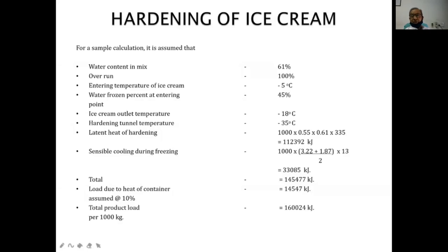The entering temperature of the ice cream is minus 5 degrees centigrade. We assume that at minus 5 degrees centigrade, 45% of the water is frozen and the remaining is required to be frozen. The ice cream outlet temperature is minus 18 degrees centigrade, and here we consider that more or less 100% of the water is frozen. It is theoretical, practically it is not. Accordingly, this is calculated for 1000 liters of ice cream. How much refrigeration load is needed for 1000 liters?